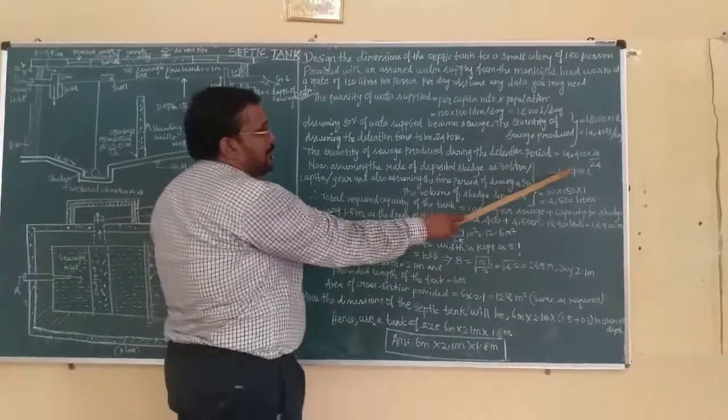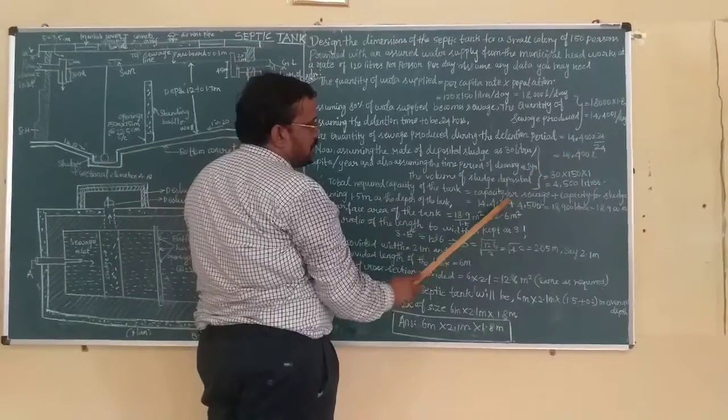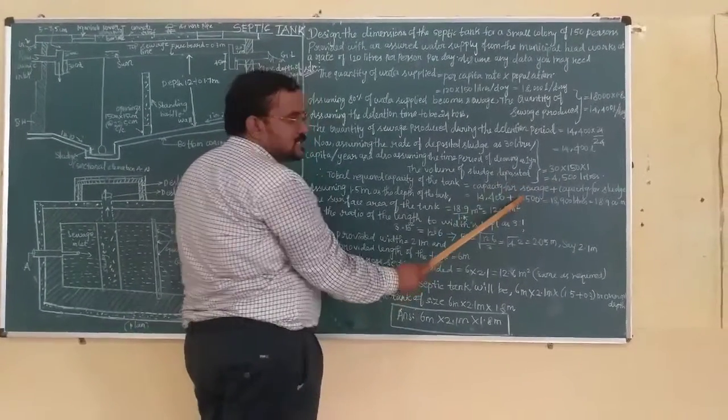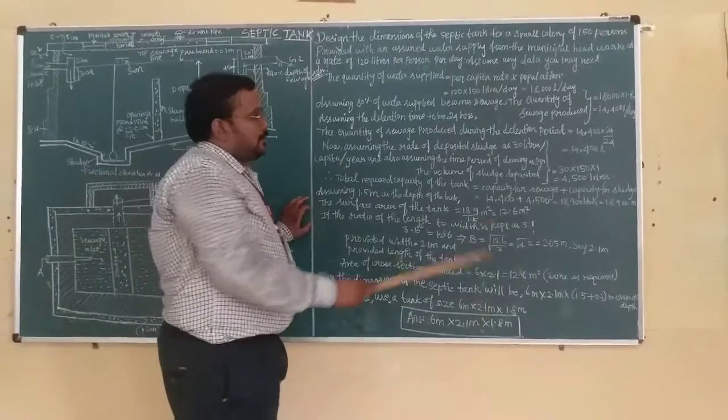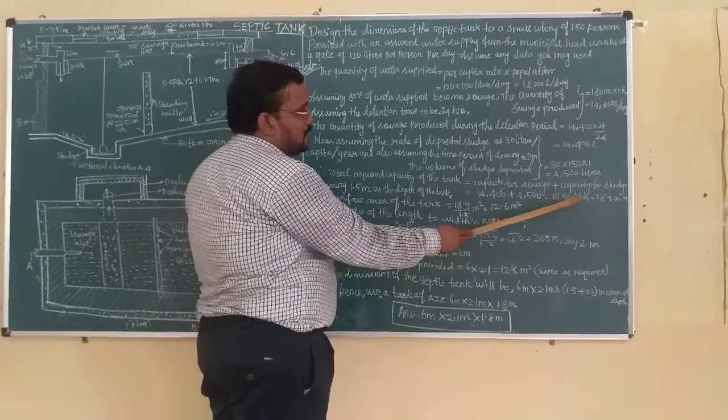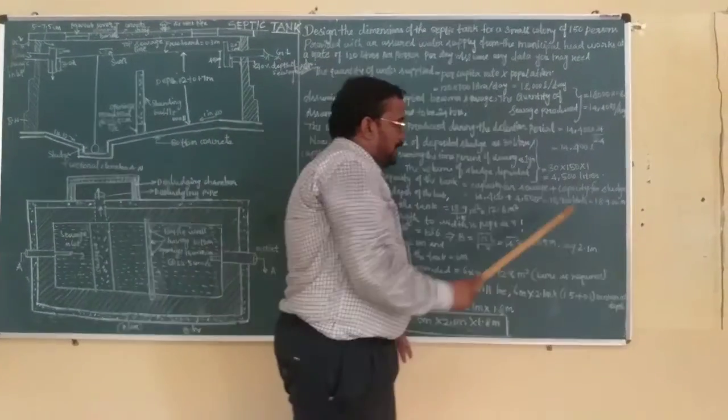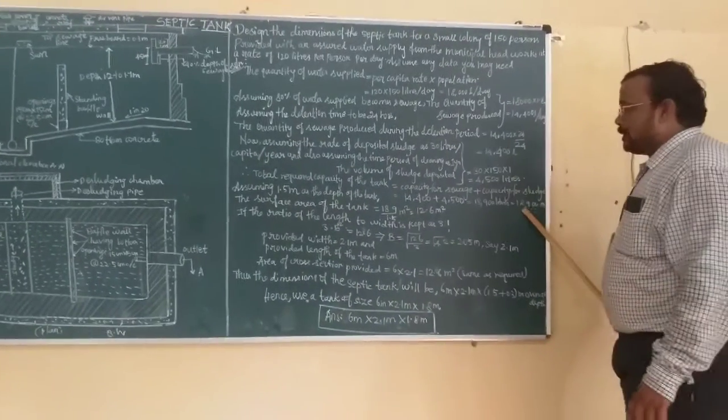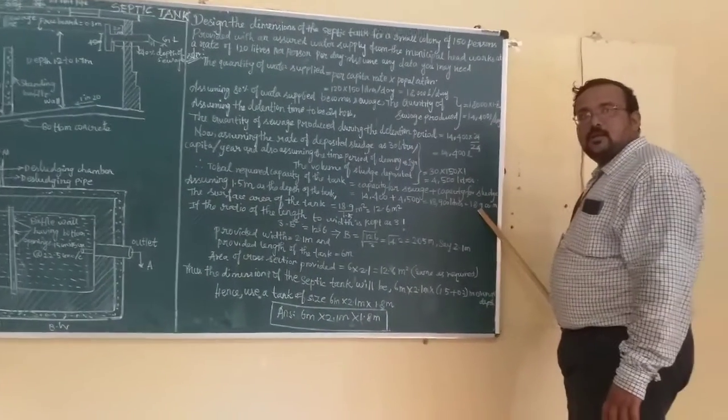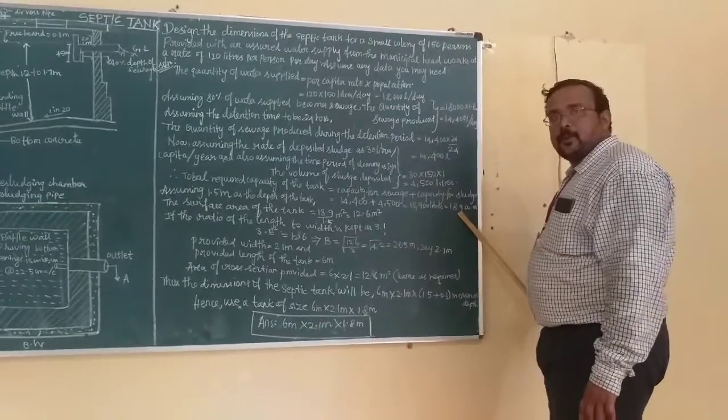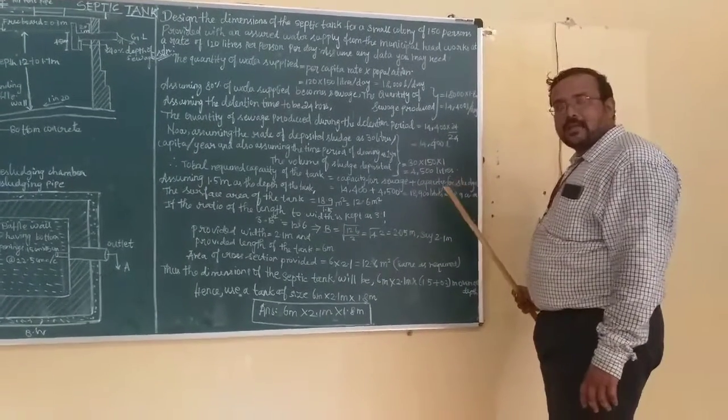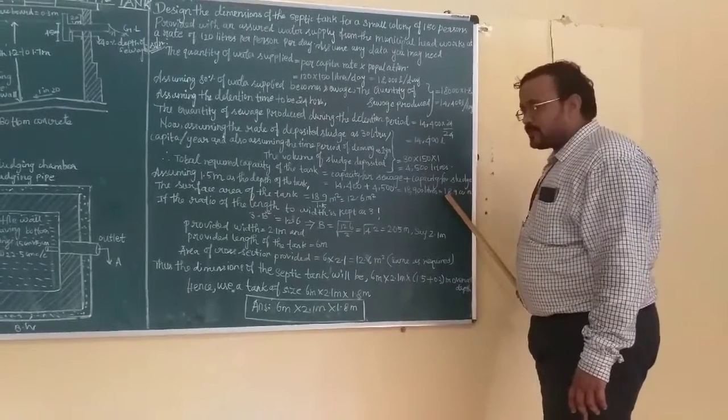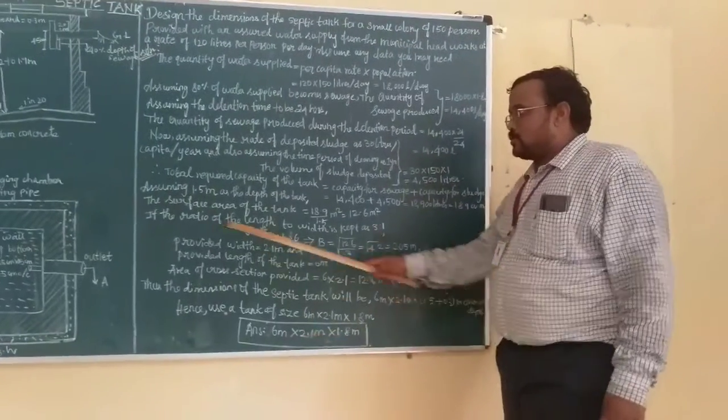So total capacity: quantity of sewage produced plus 4,500 liters sludge - sewage plus sludge - that will give you 18,900 liters. We have to have a volume of 18.9 cubic meters. Volume of sewage and sludge together. We have to have a septic tank which accommodates 18.9 cubic meters. The tank should be 18.9 cubic meters.